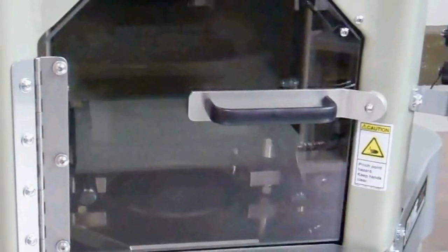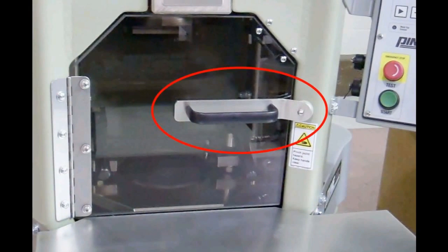First, unplug the power cord from the G2 and from the wall outlet just to be safe. First thing we'll do is install the door. We have to remove the old door from the G2, but we want to save the handle and the magnetic safety switch actuator because we'll use these on the new door.